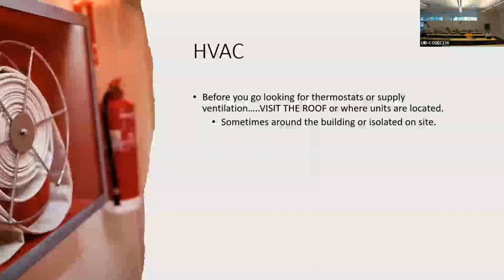Now, before I get into the HVAC side of it, as far as taking light level measurements or measuring room dimensions, you generally only need to do that in 25 to 30% of the spaces. And of that, you want to get what I would call anchors, the big ones. So if you have an open office area that's 3,000 square feet, take quite a few lighting measurements in that and measure the dimensions of the room, to verify the accuracy of the floor plan we have on hand. Also, that's the cut sheet for the lights that were installed. The manufacturer says there's supposed to be this much output at this power percentage. Does that make sense for what it's designed at?